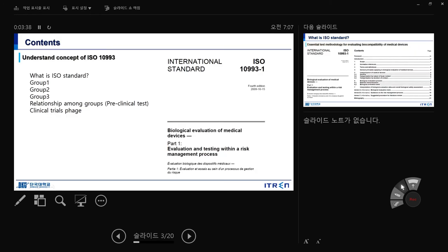You may not be familiar with ISO standard 10993. If you want to pass your biomaterial into the clinical market, the first step is to evaluate your biomaterial's safety according to ISO 10993 — please remember this number. The title is 'Biological Evaluation of Medical Devices.' It consists of multiple parts; for example, part 1 is about evaluation and testing within a risk management process. This standard is also published in French.